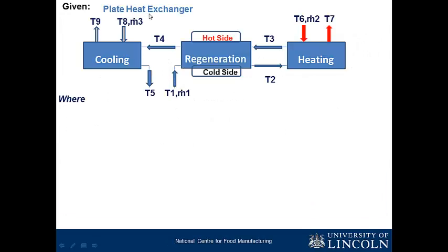We are given the plate heat exchanger. It has 3 different sections: cooling, regeneration section, and heating section. For us to understand the problem, you need to understand the working principle of a plate heat exchanger. The whole essence of the regeneration section is to bring about saving energy. You've heated your product here. Rather than sending it to the cooling section, you send it via the regeneration section in order for the raw product to extract part of the heat in the processed milk.